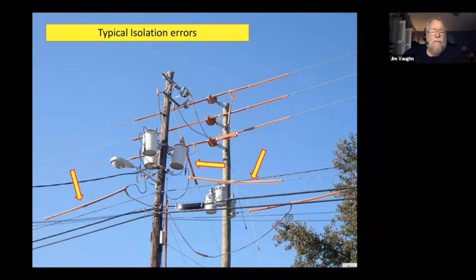Now, they've done a pretty good job of covering up the primary over on this side, but they haven't done much work about the secondary. Now, that's a little bit of that drift that I was talking about, because as linemen, we get up into this 13, 15, and 23, and especially if we get into transmission work, and we start to really lose respect for what happens on the front of a low voltage transformer. The fire here and the current here kills you just as dead as primary, and the fire sometimes is even bigger than that. So they've done a lot of cover up, and this was in the middle of a preparation for a transfer that was being done that I took off of the job site.